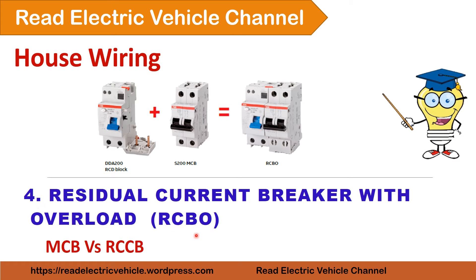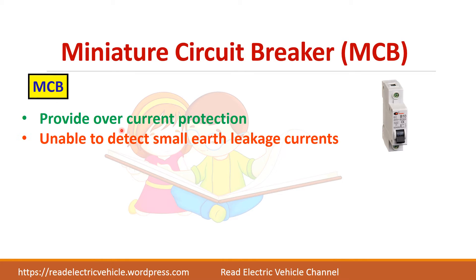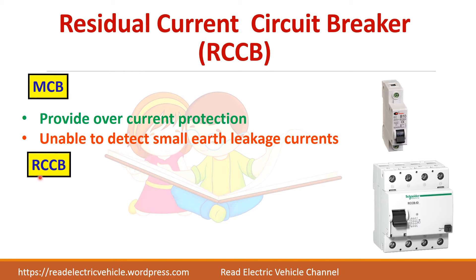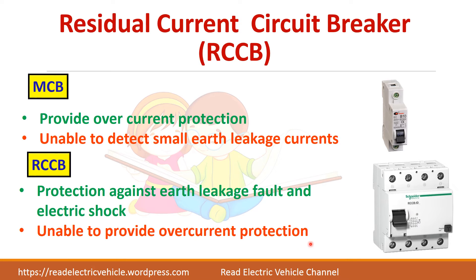In this video, let us see about the RCBO, which is also called a residual current breaker with overload, and we will see the difference between an MCB and RCCB. The MCB is mainly used to provide overcurrent protection, but its main drawback is that it is unable to detect even small leakage current. So we need another device that can detect small earth leakage current. That function is performed by the RCCB, which can detect earth leakage current and protect us from electrical shock, but the disadvantage of RCCB is that it cannot provide overcurrent protection.